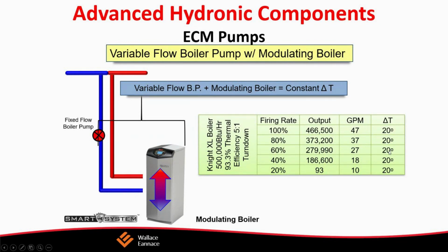So for example, here we have a 500,000 BTU boiler, which runs at about 93% thermal efficiency. Let's assume it has a 5-to-1 turn down ratio. So the output is 466,500. At a 20-degree delta T, we would have 47 GPM going through that.